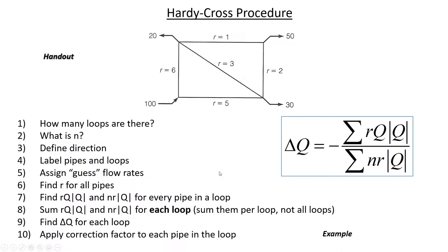Just as a reminder, the procedure is to examine how many loops there are and to determine what n value is being used. Both in this earlier example and the one I just handed you, there are two loops. We use n of 2 when using the Darcy-Wiesbach equation for friction loss. You'd use an n of 1.85 if you're using the Hazen-Williams equation. Clockwise is positive — that's how we determine whether a flow is positive or negative when we put it in the spreadsheet.